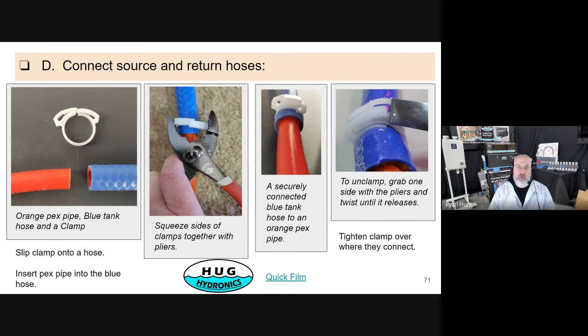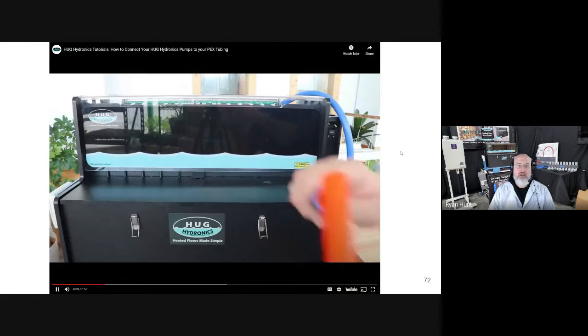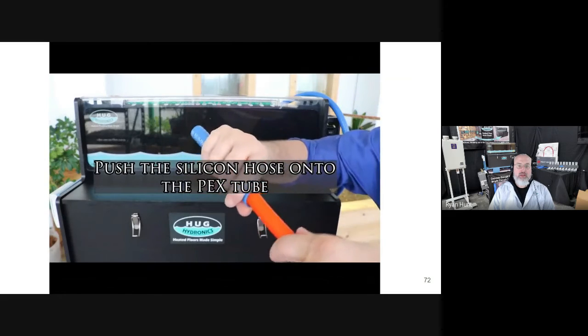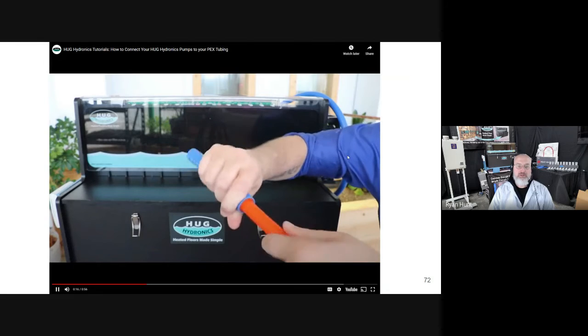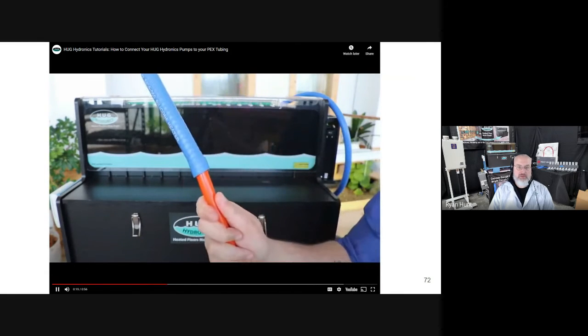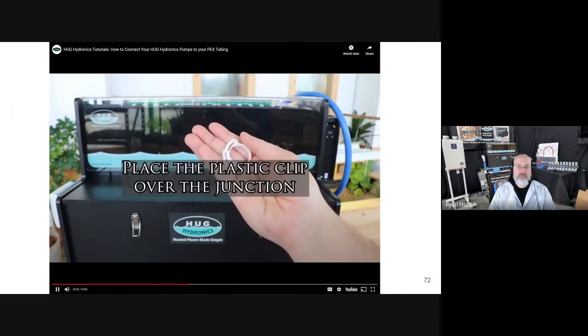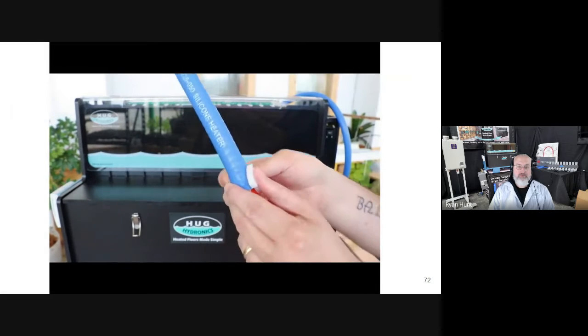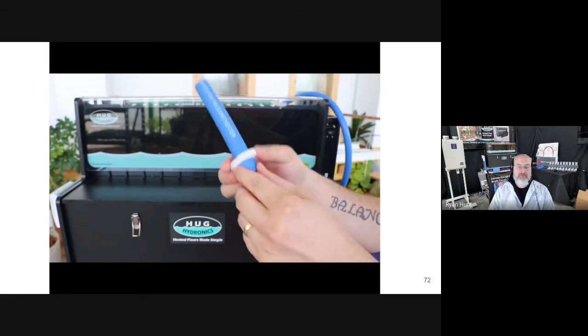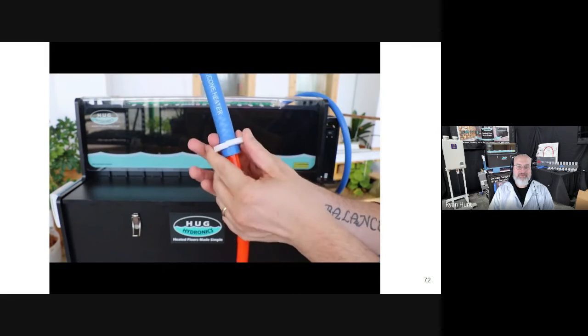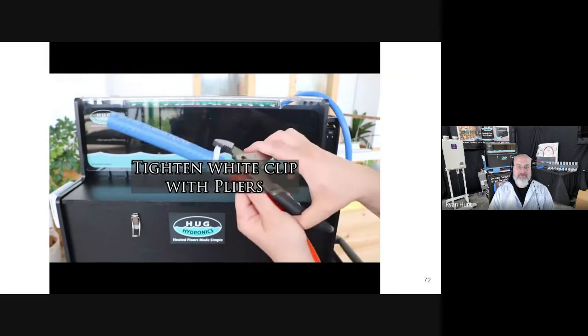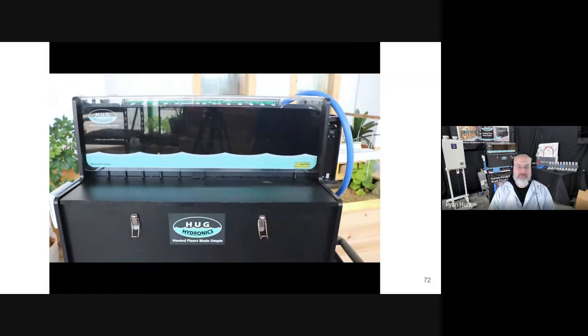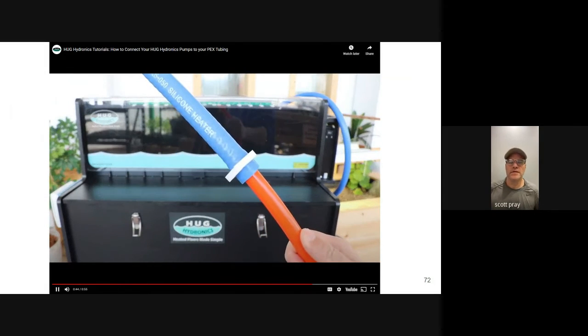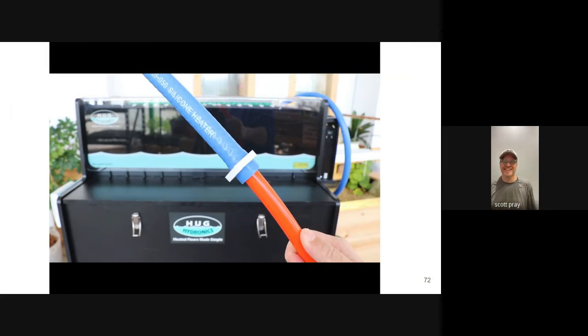To unclamp it, you can grab one side of the clamp and you slide it sideways, and the little teeth just slide apart and it pops loose. Okay. All you need to do is firmly push and twist the silicone hose onto the PEX tube as far as you're able, usually about 1 inch. Next, you'll need to find your plastic clamp. These will come with your unit. Then, attach it where the junction occurs, and then tighten with your hands. Then, tighten with a pair of pliers. Repeat as necessary for all PEX tubes coming out of the ground.